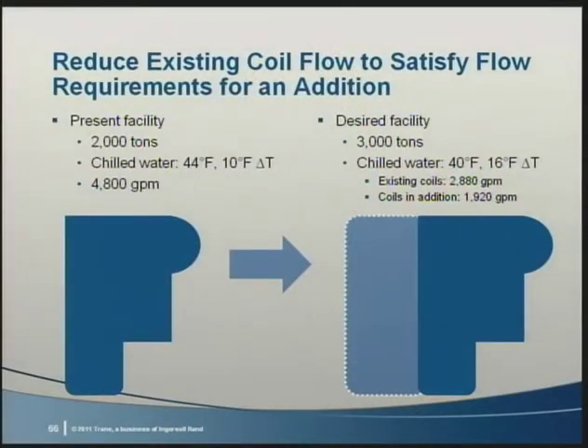And they were able to use the existing pipes and pumps just by selecting the new, higher capacity chillers at the proper conditions. As we worked on the job, there were a couple of things that we had to watch out for. The first was pipe insulation.